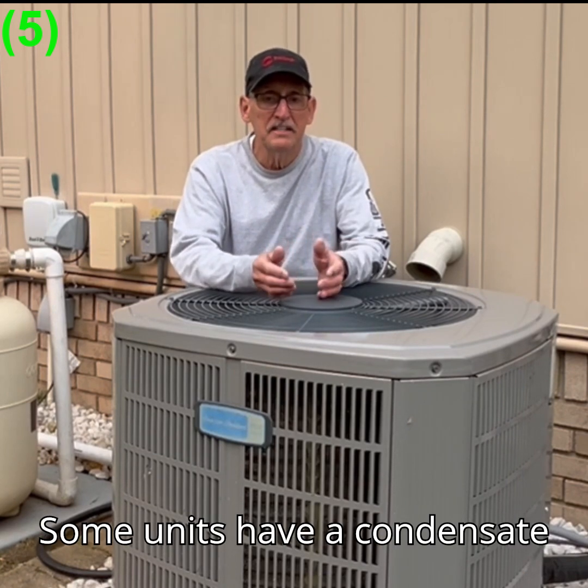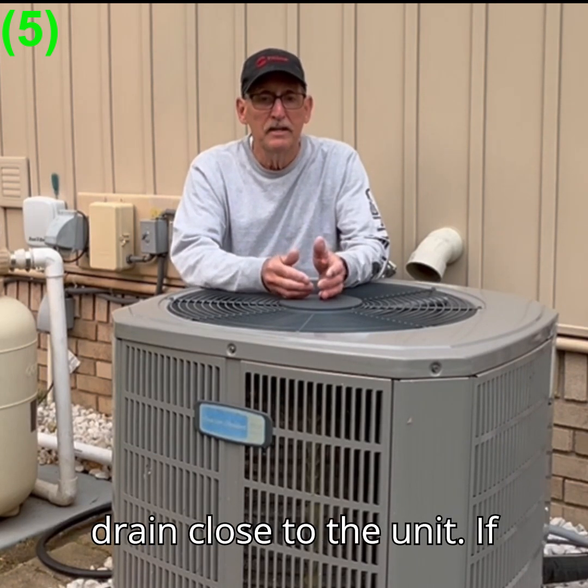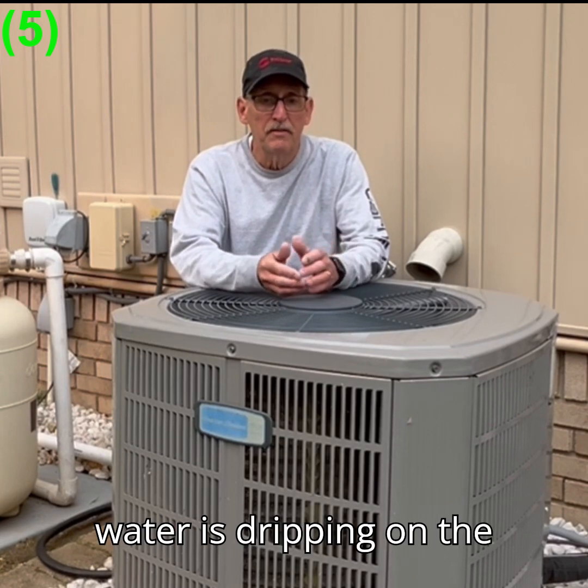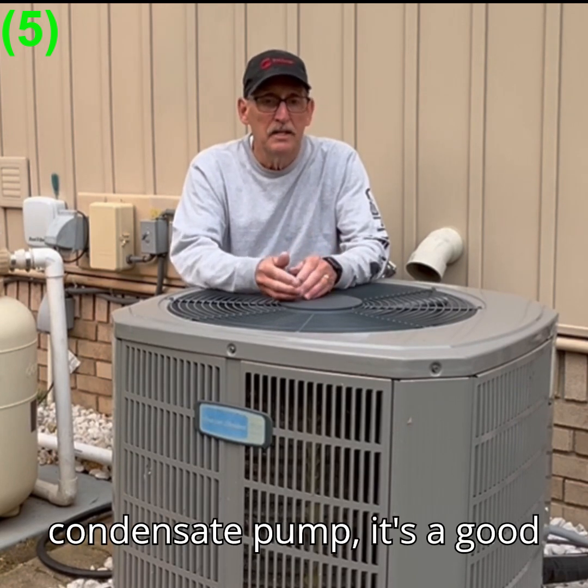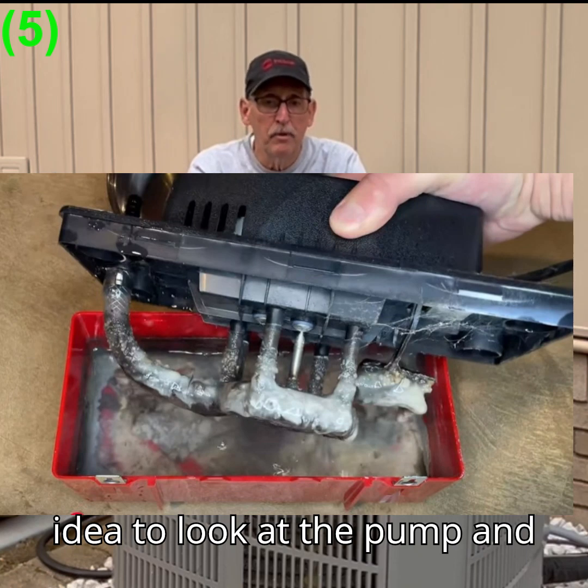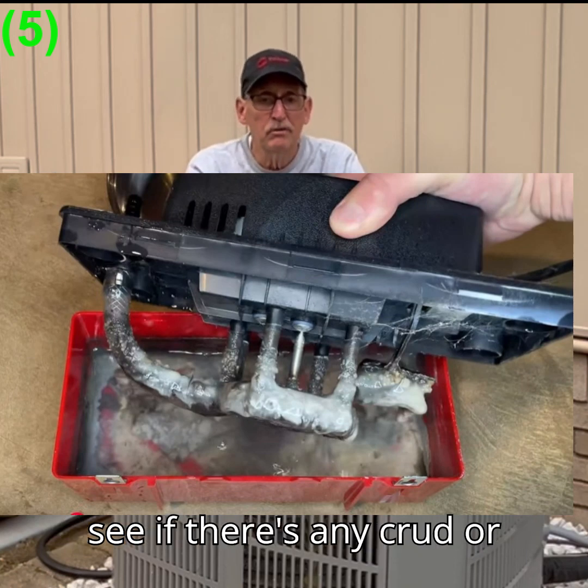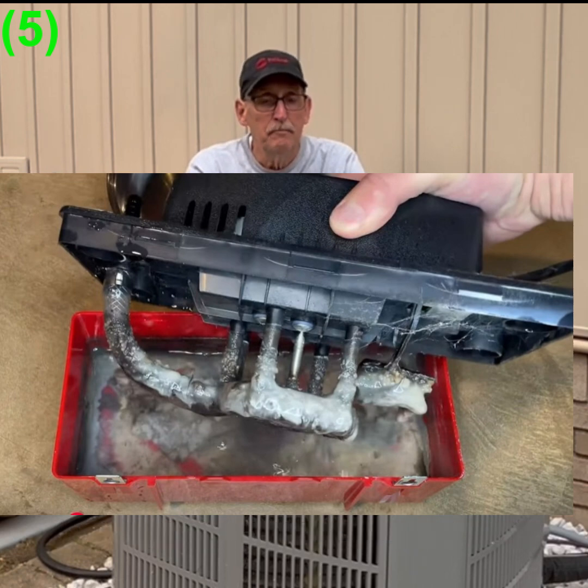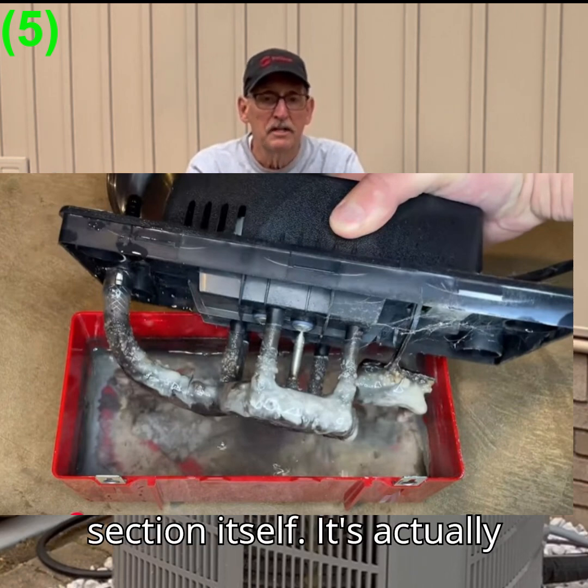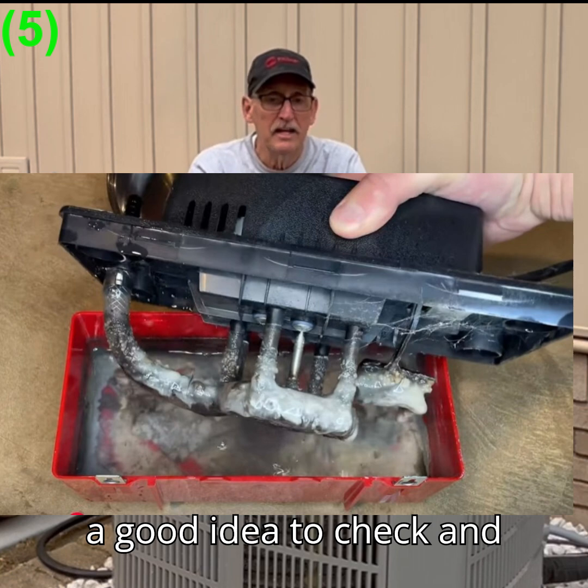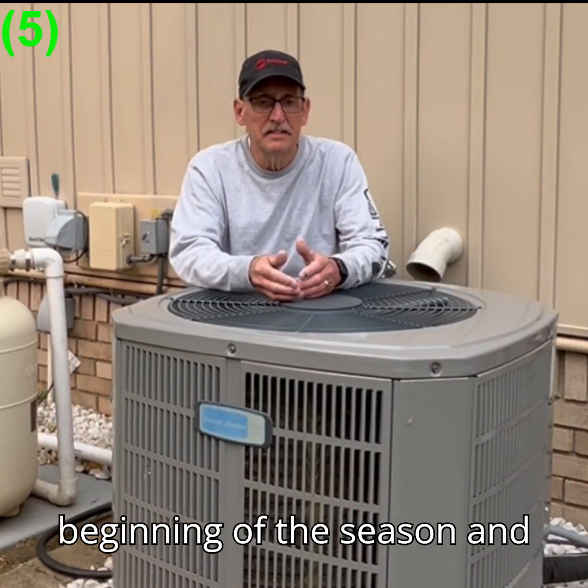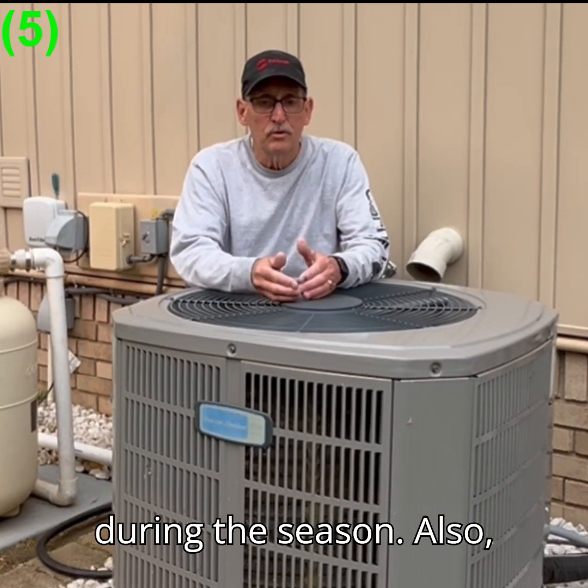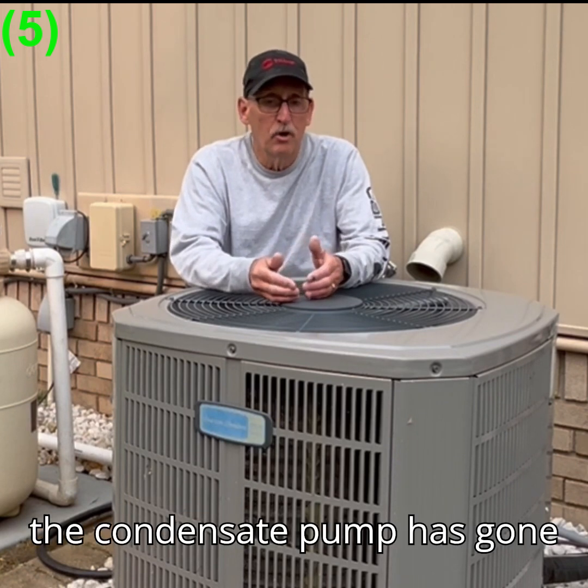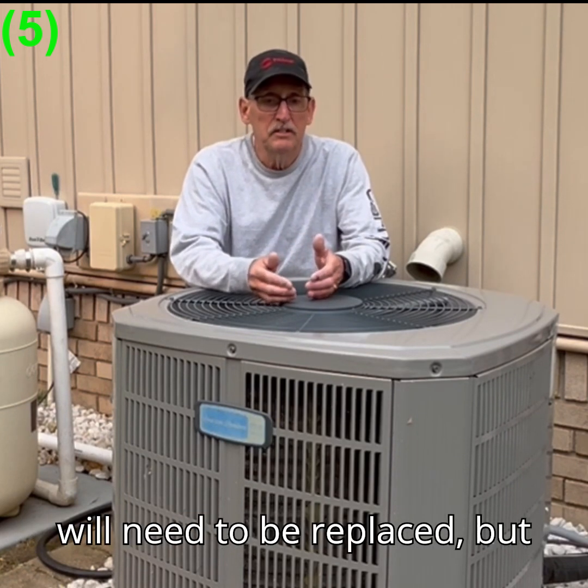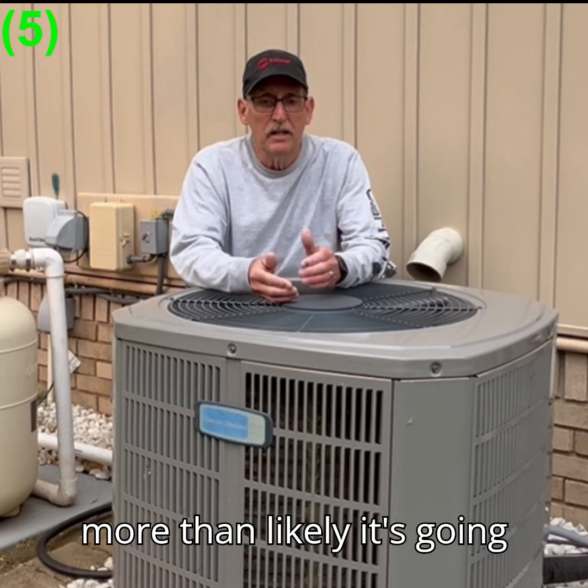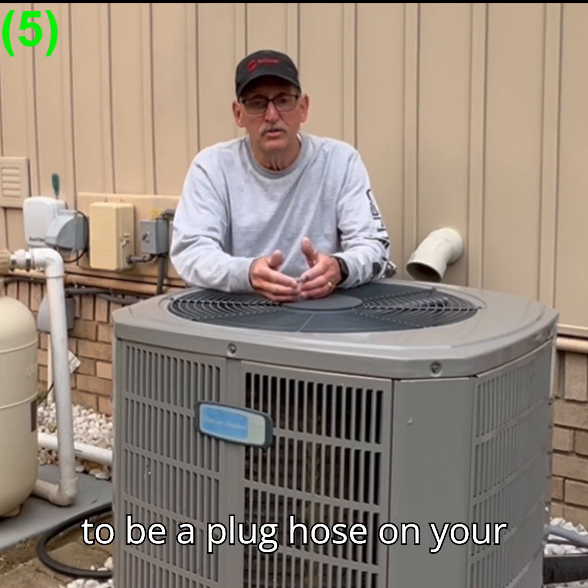Some units have a condensate pump because there's no floor drain close to the unit. If water is dripping on the ground and you have a condensate pump, it's a good idea to look at the pump and see if there's any crud or junk that's developed in the pan itself, in the pump section itself. It's actually a good idea to check and clean the pump at the beginning of the season and during the season. Also, there's a possibility that the condensate pump has gone bad. If that's the case, it will need to be replaced, but more than likely, it's going to be a plugged hose on your furnace.